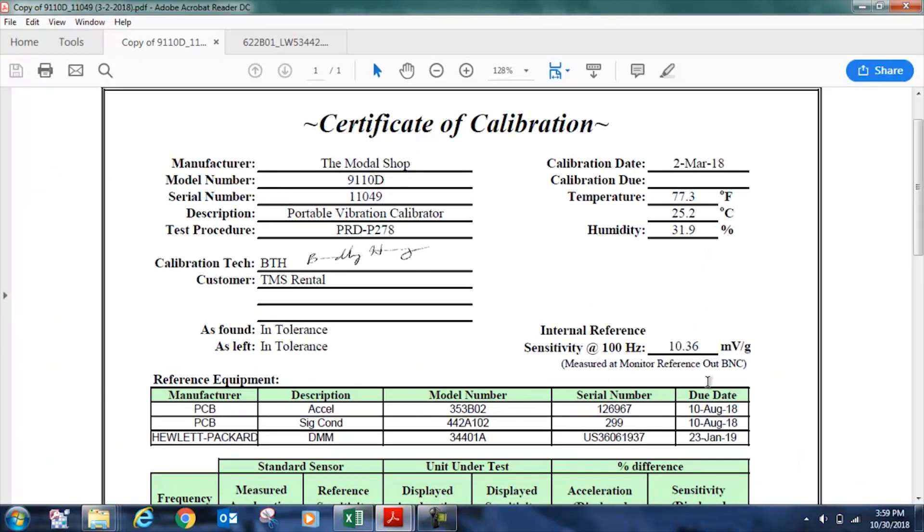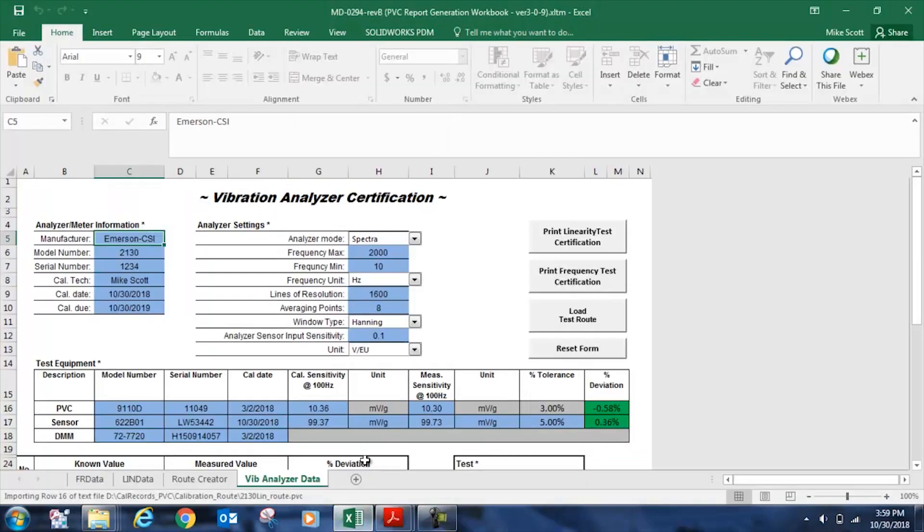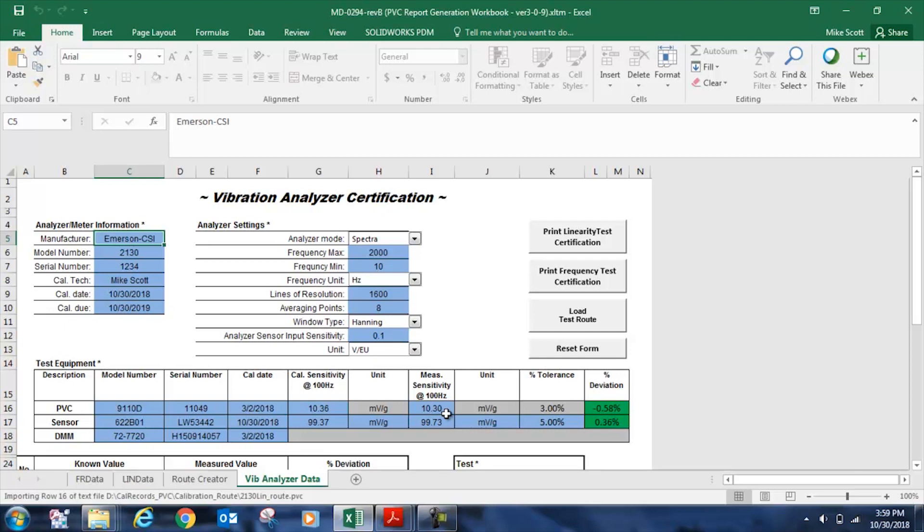You can see mine here, and I draw your attention to the internal reference sensitivity at 100 hertz. On March 2nd, 2018, it was 10.36 millivolts per G. On October 30th, the day this video was shot, the sensitivity was measured to be 10.30 millivolts per G at 100 hertz at 1g RMS. So I've documented that here, and that gives us a percent deviation of 0.58%. You notice that this cell is green.